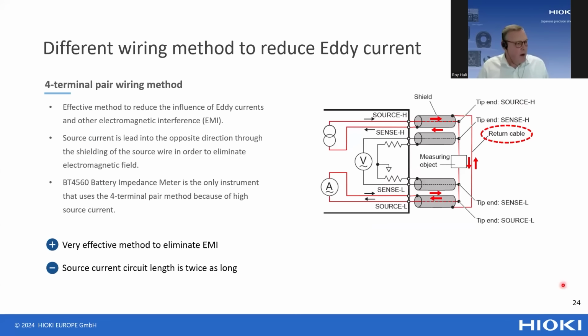There is also another wiring method called the 4-terminal pair wiring method. We use this method specifically for one battery tester, the BT4560. This battery tester can measure the internal resistance of a battery at 1 kilohertz, but is also able to measure at lower frequencies, for instance about 1 hertz. When you measure at 1 hertz, you can identify the electrode and the reaction resistance of the battery, and therefore it's also quite popular in the production lines of high-end battery cells.